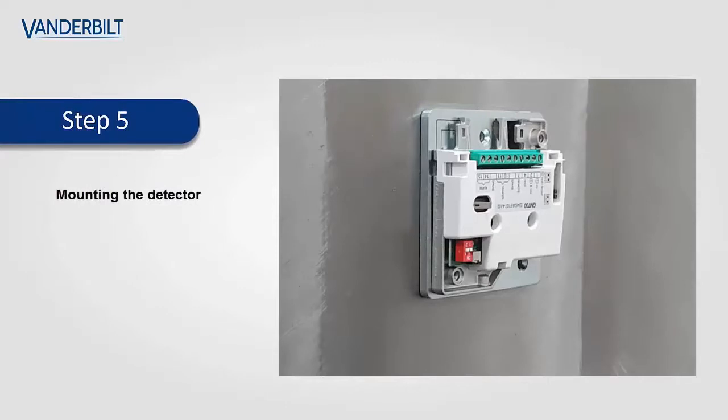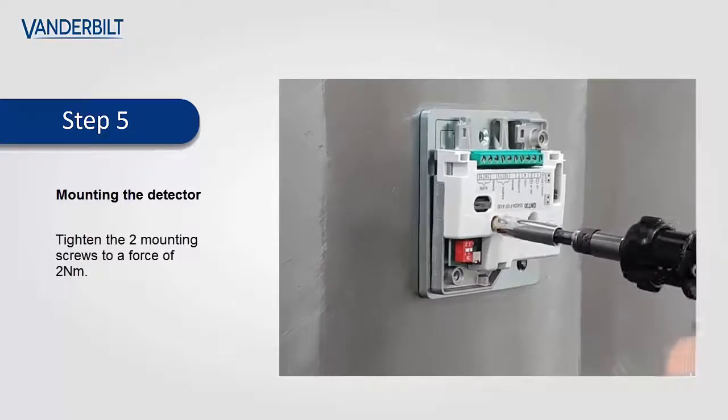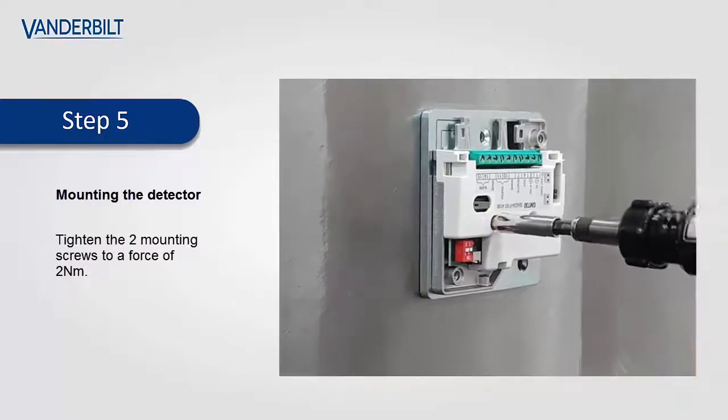As detailed in the installation sheet for the detector, the two securing screws should be tightened to a force of 2 Newtons. For this you will require a torque screwdriver.